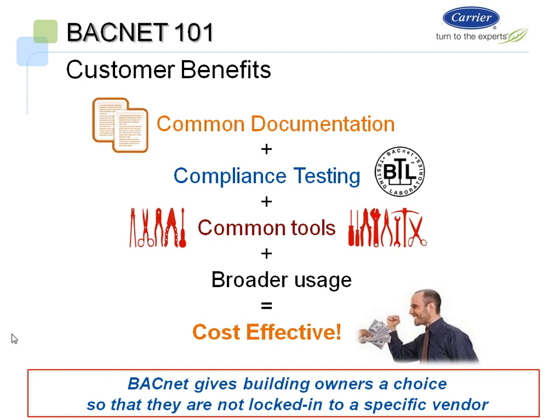Summarizing interoperability and customer benefits: there is common documentation for the BACnet standards, rules, and specifications, as well as documentation for any type of controller that can speak BACnet, covering displaying points, how to integrate properly, and what points to reference. You have tools like the Auto Discovery tool that let you access and auto-discover points speaking BACnet, just following the regulations.